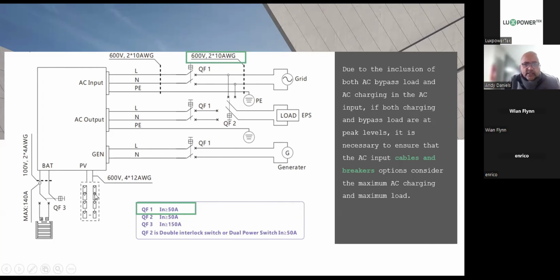And then here we have our PV input. As discussed previously, we're going to go through a surge protection device, fuses, fuse holders, and the DC circuit breaker. And then this is your battery bank here with a dedicated rated circuit breaker, minimum 140 amps.